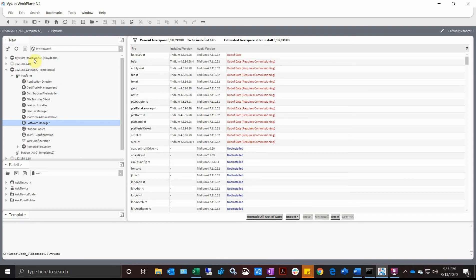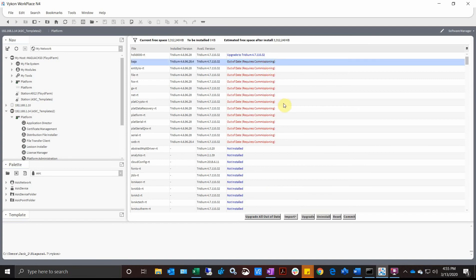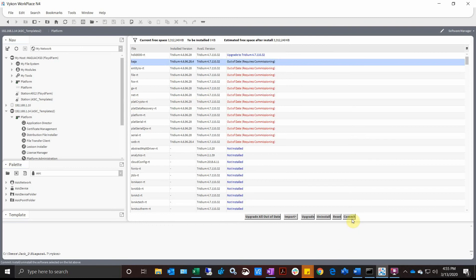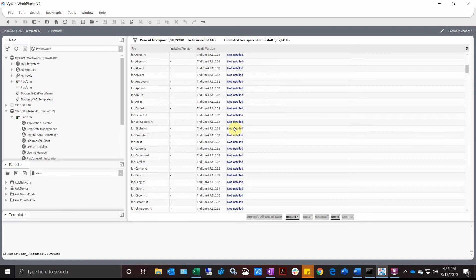I'm going to say Update All Out of Date. This one is going to require commissioning because it is core software. If there are certain modules in here, sometimes it might just transfer, but if it says Requires Commissioning, we're going to go into the commissioning wizard. And there goes that one. Okay, so it didn't go into the commissioning wizard. It just installed the ones that were out of date.